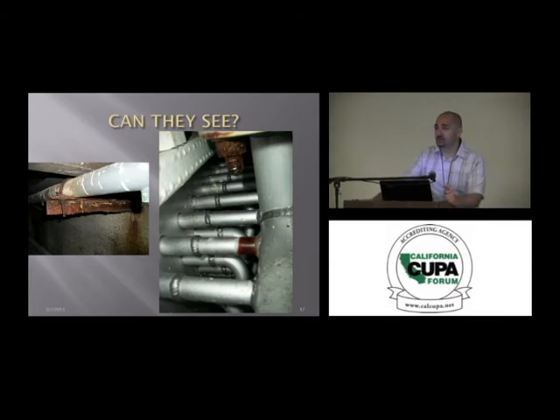a carbon steel support that is supporting the ammonia line. Or I'm sorry, that's not the ammonia, that's a defrost water line, but that corrosion is falling down on the coil, causing electrolysis. Any metal contact with aluminum will cause electrolysis, cause it to corrode, weaken, and cause an ammonia leak to develop. Again, on the right-hand side, you got a carbon steel bolt corroding. You can see where it's dripping onto that pipe. That bolt's not changed. If it doesn't corrode fast, I should say, it's going to cause an ammonia leak on that ammonia pipe there that you see.